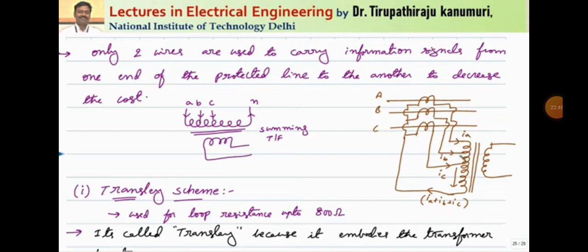Under balanced conditions, the phasor sum of the three currents is equal to zero, so no current passes through this winding. Whenever there is an imbalance in the currents — that means if the sum of the currents is not equal to zero or some fault happens — only then will the net effect be transmitted to the secondary of the transformer. This transformer is called the summing transformer. Using this summing transformer, only two wires are sufficient.